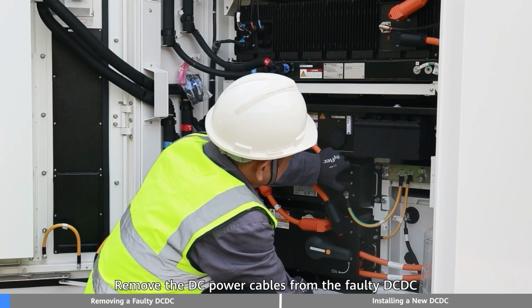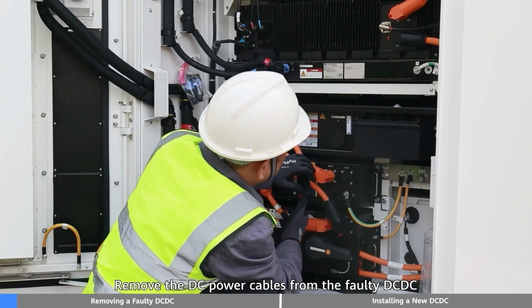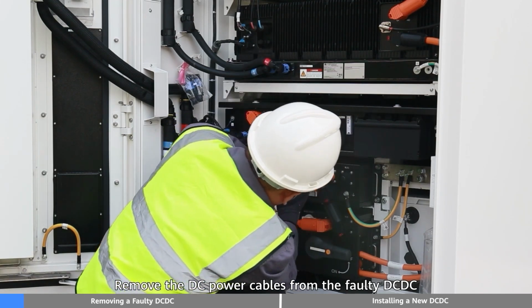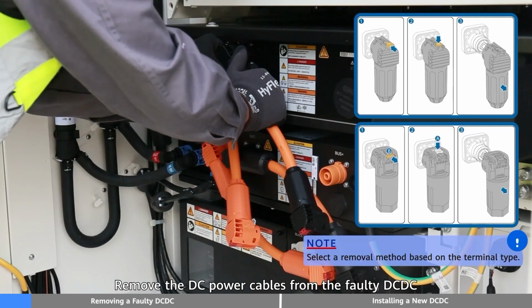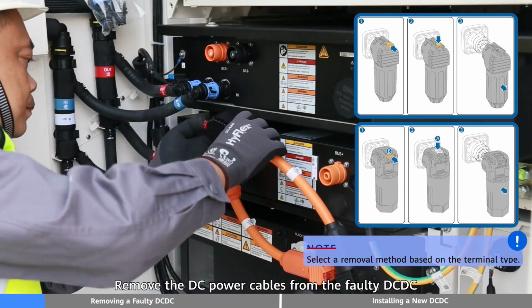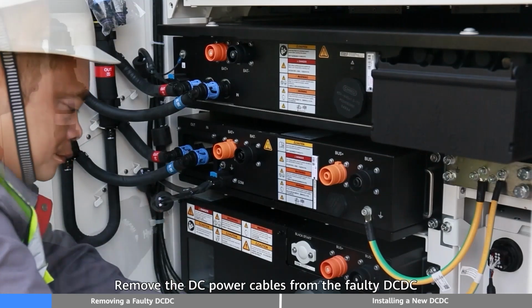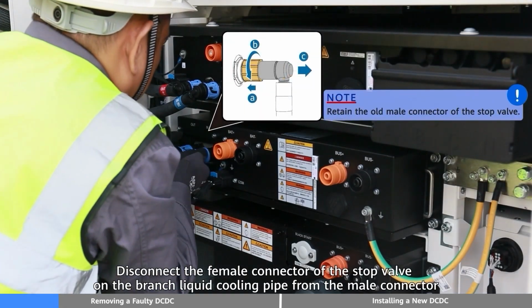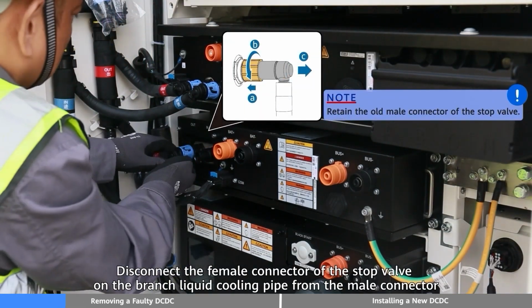Remove the DC power cables from the faulty DCDC. Disconnect the female connector of the stop valve on the branch liquid cooling pipe from the male connector.